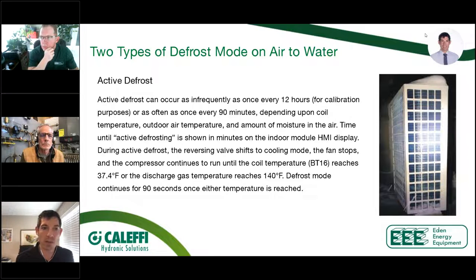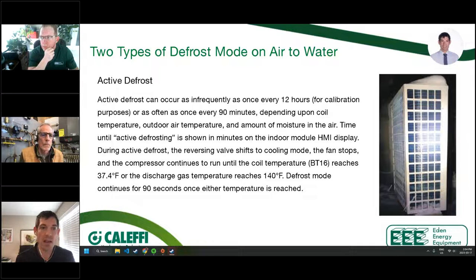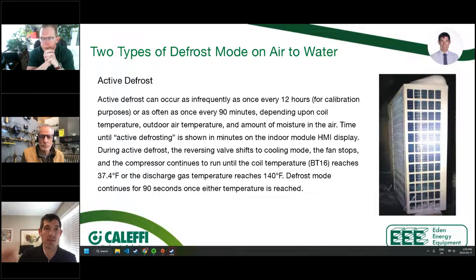One of the things that my dad was mentioning that is a nuance here is we're taking water that we heated, hopefully, with a COP of 3 or 4. To do that, in older versions of air-to-water heat pumps, you might have had electric resistance to keep it from freezing, but you're talking about a COP of 1 at that point. So you're using just an electric water heater to make sure that thing doesn't freeze outside. Now, instead, we can use water from our buffer tank potentially that we've heated with that higher COP just for a minute to make sure it doesn't freeze up.